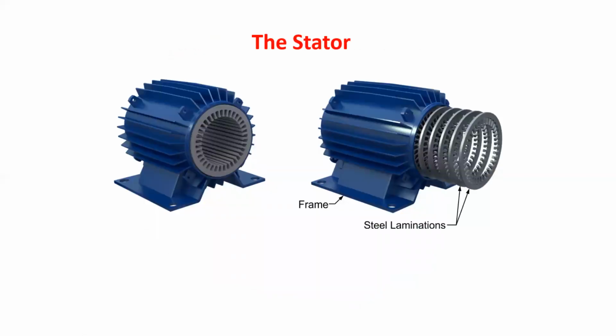The stator is enclosed in the main housing of the frame. So this is the frame, and often it has these funny fins on it. These might be a bit exaggerated, and this is to ensure that the heat can be dissipated readily from the motor. Heat is a motor's worst enemy. The stator is made up of the same type of laminations that we saw on the rotor and that we are accustomed to seeing in transformers.